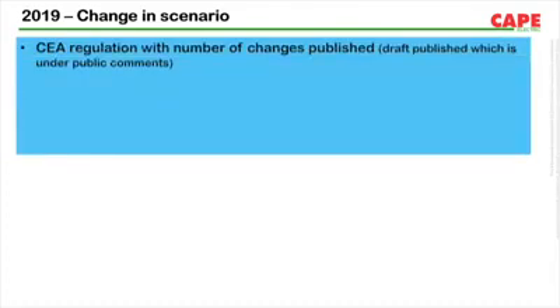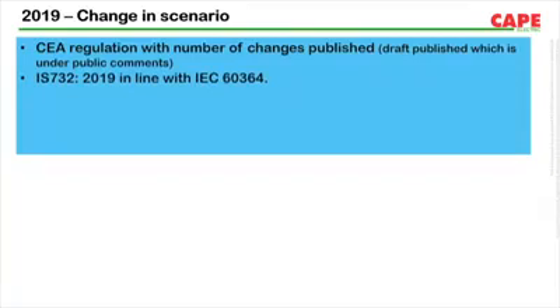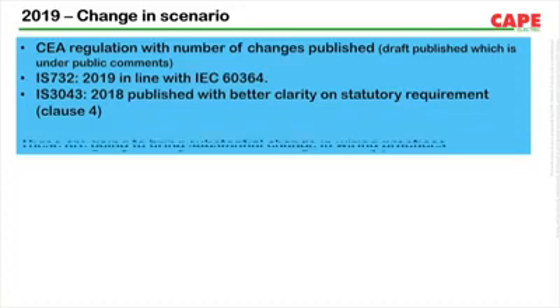In 2019, the situation started changing. CEA has published a new draft amendment on the regulation, Measures Relating to Safety and Electric Supply Regulation 2010. I think it is the fourth amendment. BIS finally published the IS 732 Code of Practice of Electrical Wiring in February 2019. This new IS 732 is in line with IEC 60364, which is going to create a new benchmark for low voltage electrical safety. IS 3043, called the Code of Practice of Earthing, a new version was published in December 2018. These new publications are going to bring substantial change in the wiring practice and are going to bring a high degree of safety if they are followed properly.